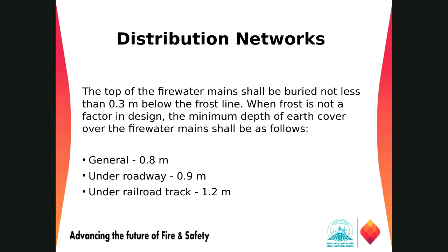And then we have the depth of pipe. What should be the minimum depth for the pipe below the ground, and below the road? If it is ground level, it should be 0.8 meter in general, in most cases. If it's any roadway, 0.9 meter, and if it is going below railway tracks, we should bury our pipe at least 1.2 meter below to avoid any kind of damage to our piping system.